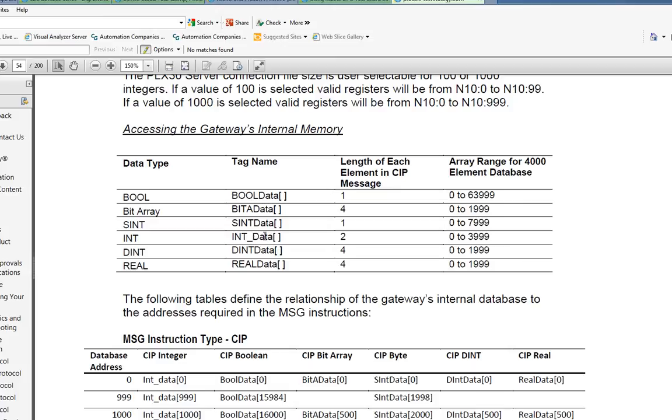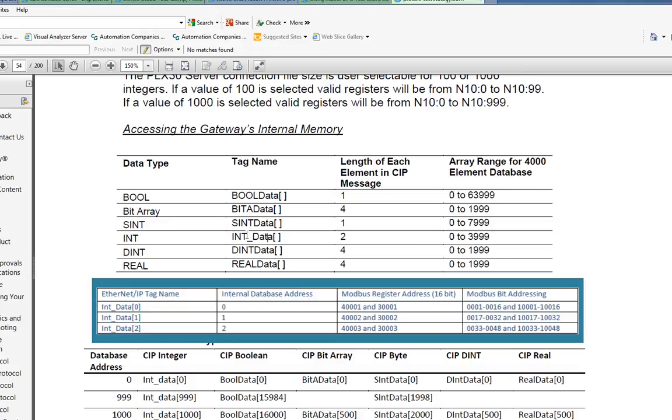I'm going to use the integers. You'll notice under the tag name we have int underscore data bracket. That's our int array and we have 4,000 registers that we can address. How do these addresses or Ethernet IP tags correspond to Modbus registers?